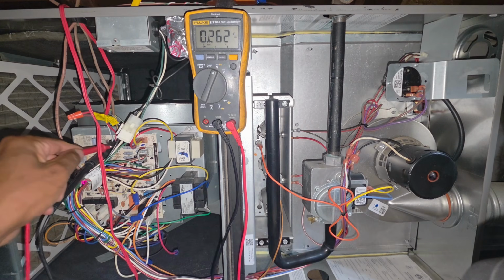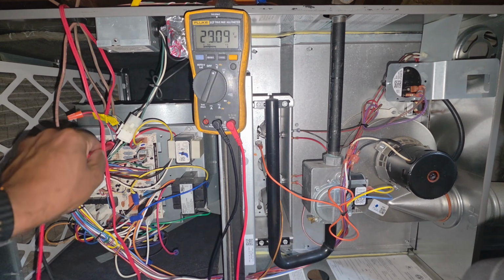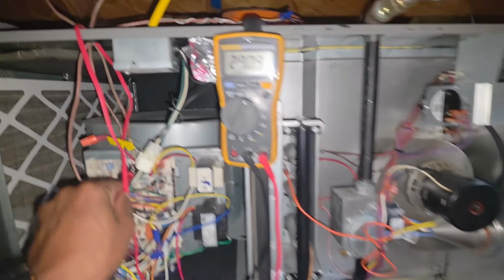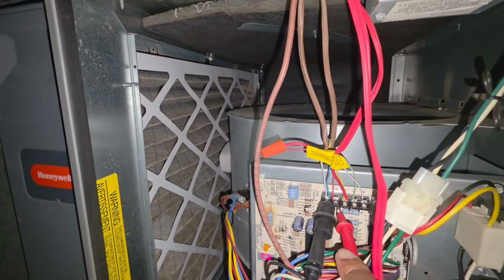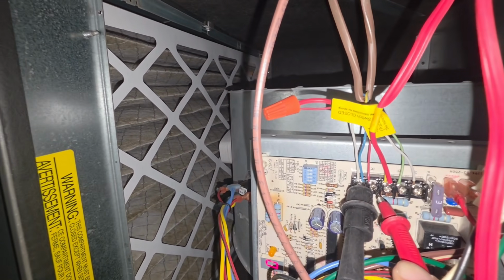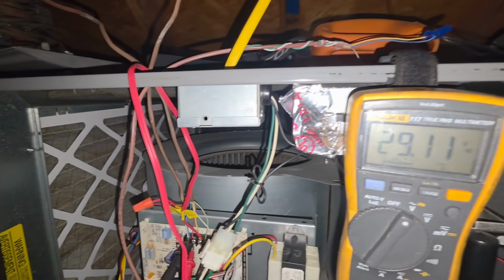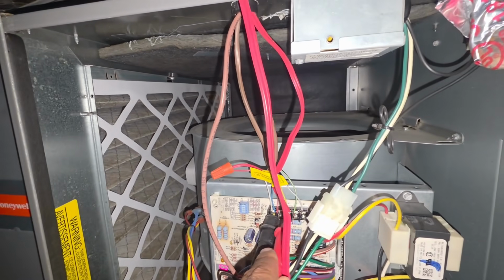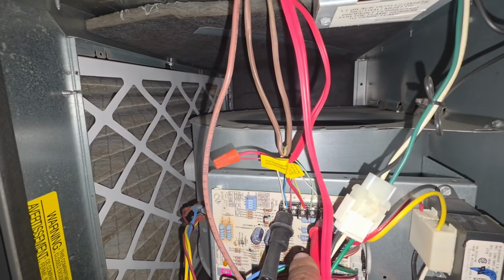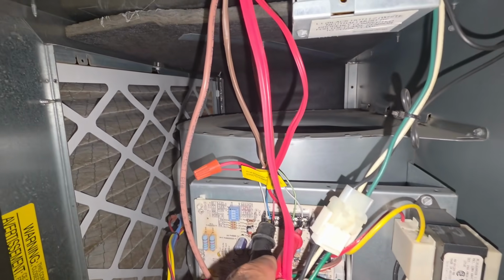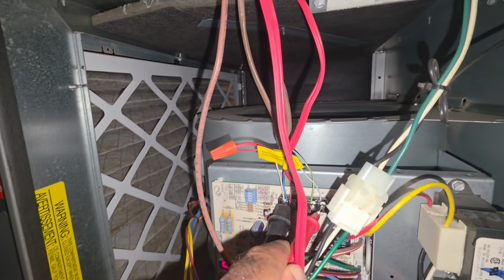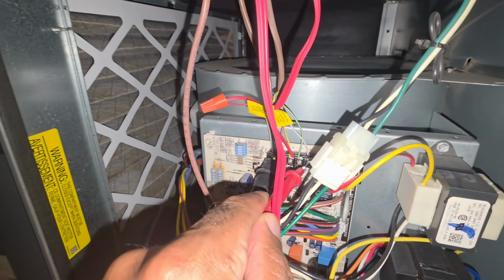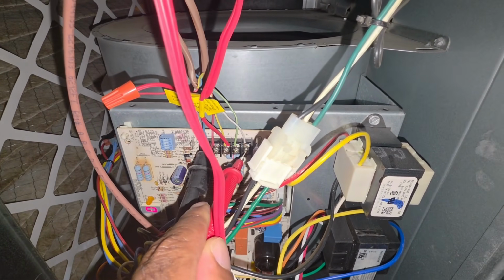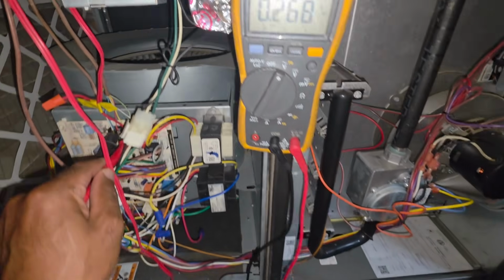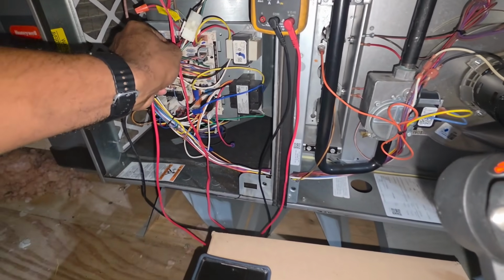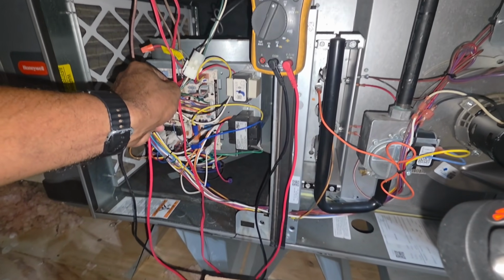So this is the pivot method right here. As you see on my meter, I'm going from common to red. Common to red. And I have 29 volts. You see, we haven't called for heat. See my W1 right here? W1. We have 0. Now I'm gonna hold my red. I still got my pivot on my common.